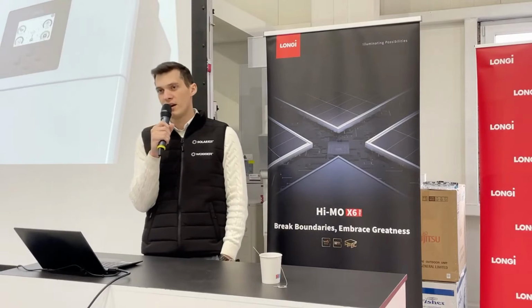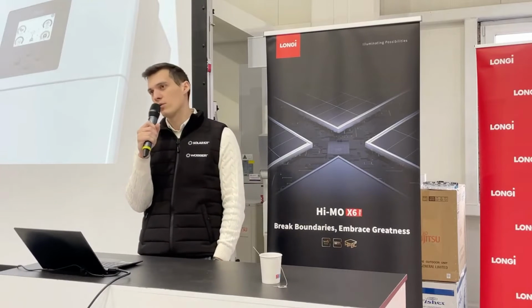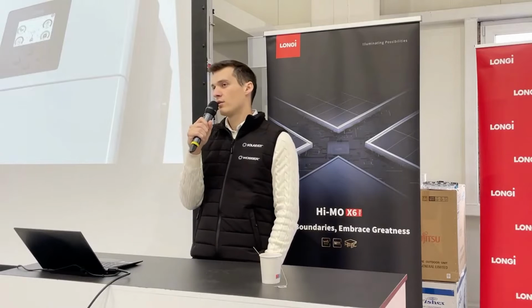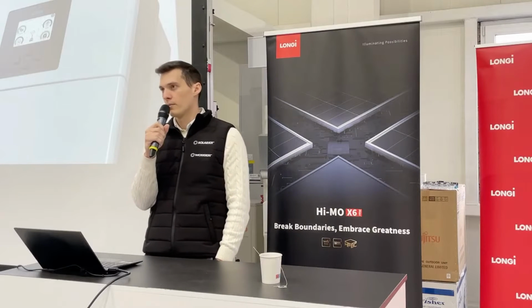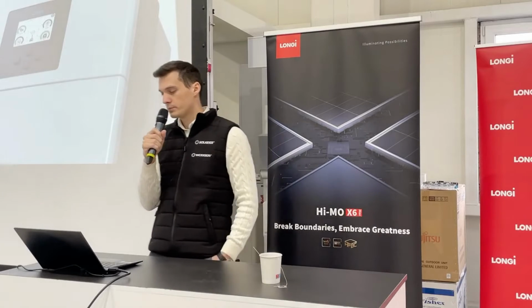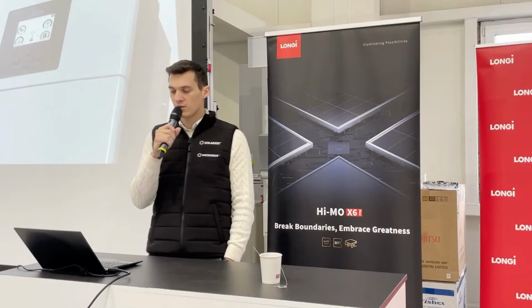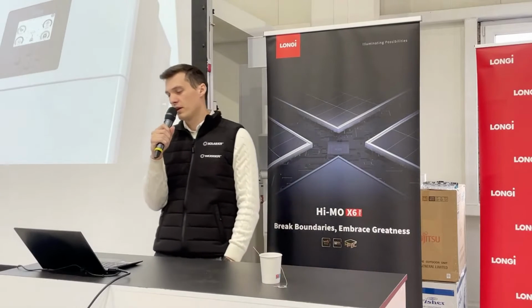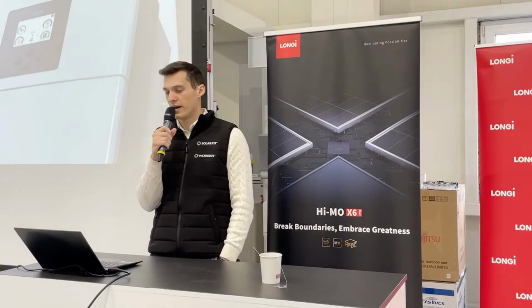From the inside, the new change is that Deye inverters until now only allowed 30% oversizing on the DC side, so with a 10 kilowatt inverter you could only use 13 kilowatts of solar panels. Now it's going to raise to 50%, meeting the industry standard of most major brands. Some inverters already allow 70 or 100% oversizing, but I believe 50 is a good enough number. I don't think you should usually go over that.